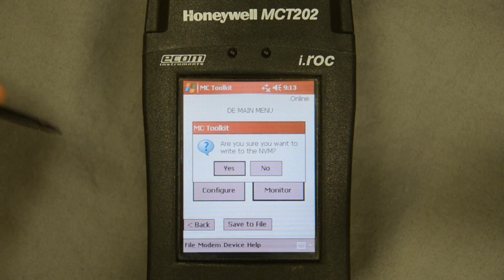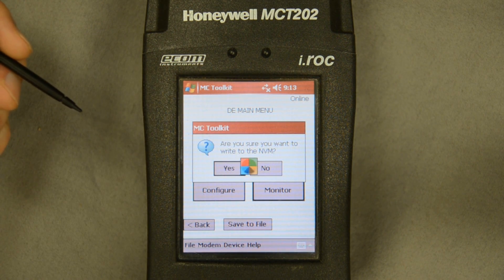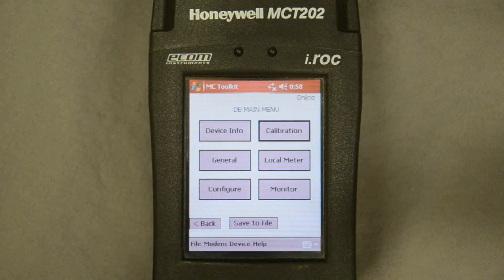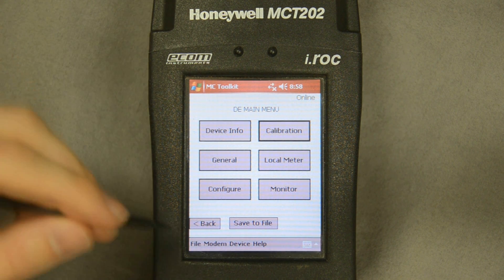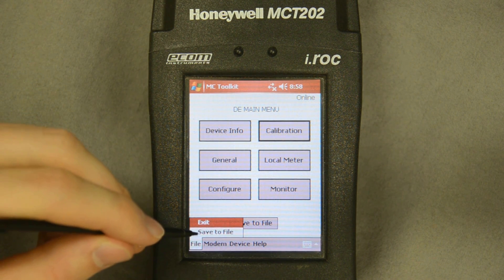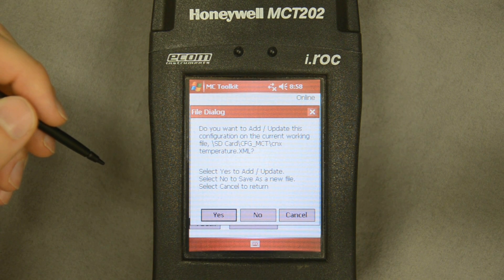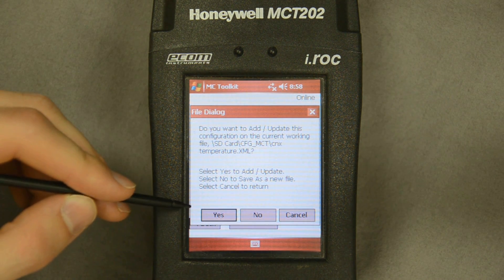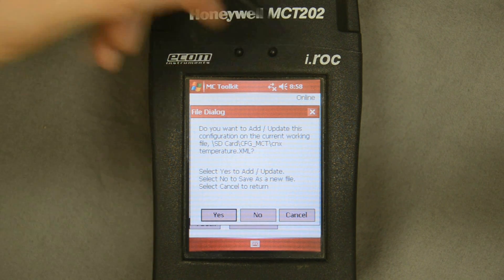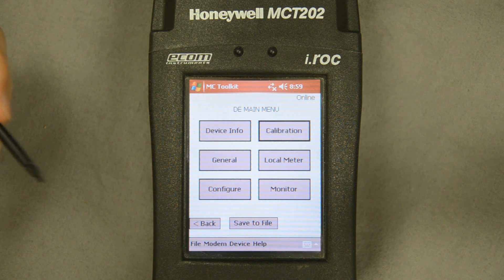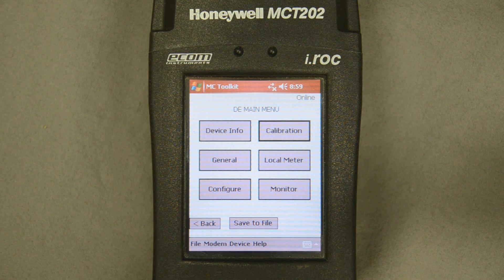The last thing I do is store it to the device so when power is unplugged it's exactly as we left it — and that was successful. Now if I want to do one more thing: I can store this configuration to the communicator itself, save it as a file, pull that file up later, work offline on that file, save it, reconnect to the transmitter, and then send that reconfigured file to the transmitter. I can do a lot of offline work as well. That's it.